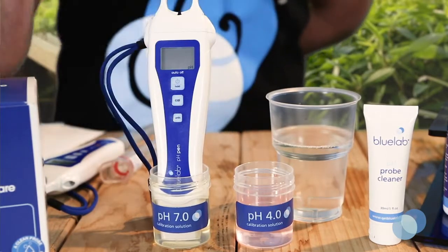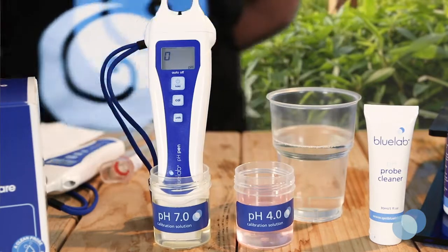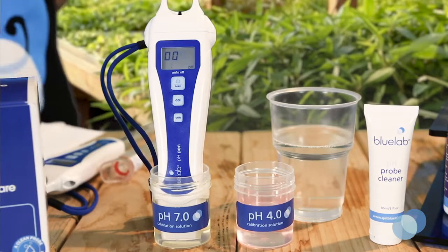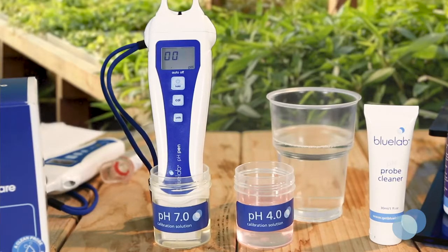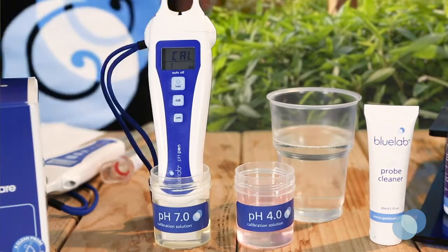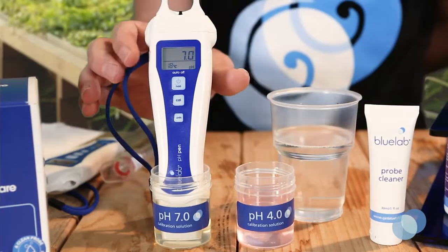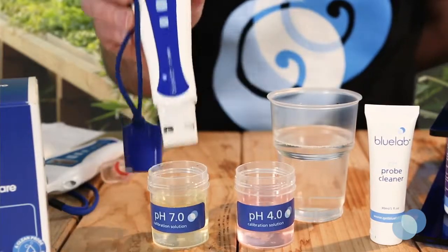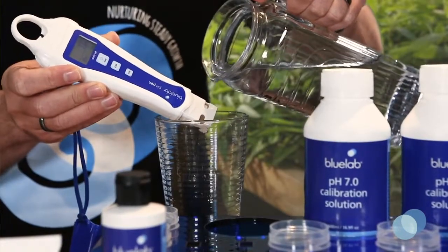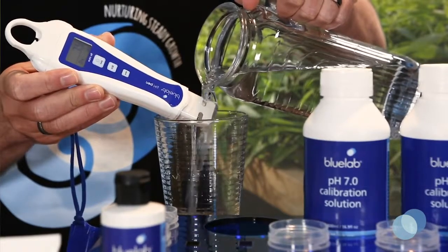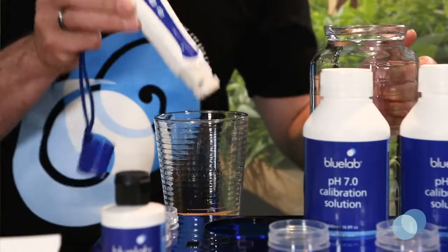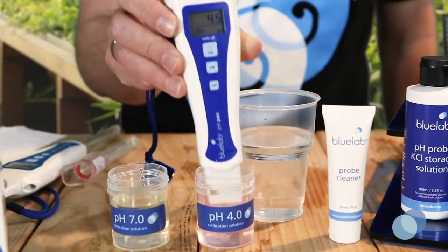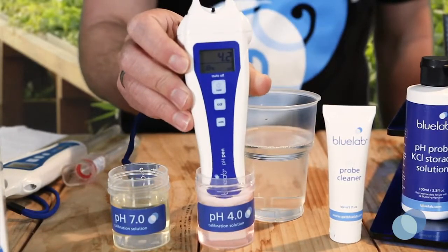Four small boxes start to flash, indicating the start of calibration. Leave the probe in the solution while the display is flashing. After the boxes stop flashing, you'll see cal displayed on the screen, showing you that calibration is complete. Rinse the probe tip in clean tap water and then gently shake off any excess water. Next, place the probe tip in fresh Bluelab pH 4 or pH 10 calibration solution.